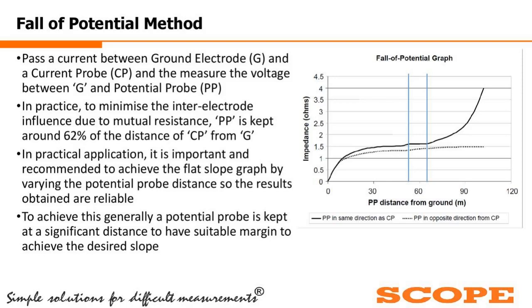the best value of resistance will be obtained when we put the potential probe at a distance of around 60 meters or so. That's the reason the majority, and we also, recommend putting the voltage probe at a distance of around 60 meters and the current probe at a distance of around 100 meters, and that also matches the formula of the 62% measurement method. So we have to pass the current between electrode G and the current probe. This is how the 62% method is explained.